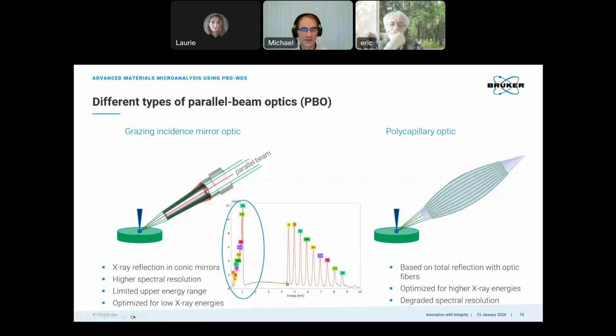So as we see here in the spectrum, peak resolution is quite nice in the higher energy range, also by EDS, but we have a severe crowd here. So it's a very strong overlap in the low energy region, and the Bruker system can resolve this.